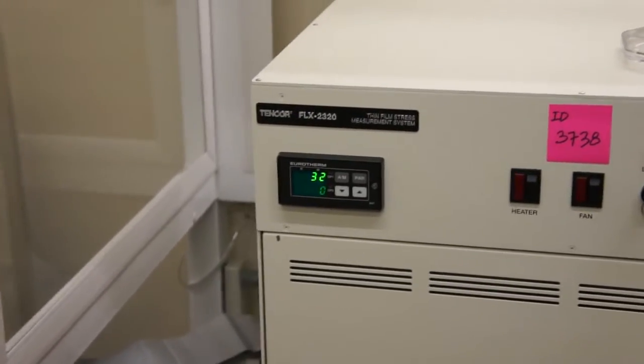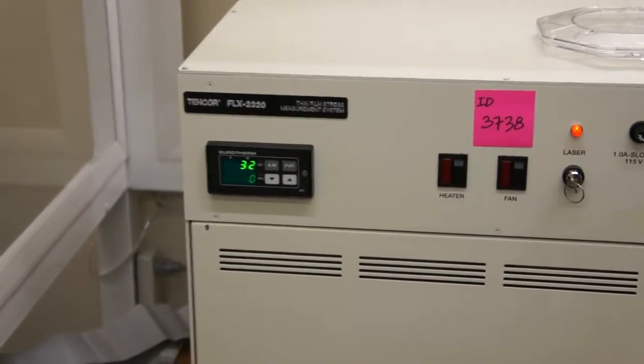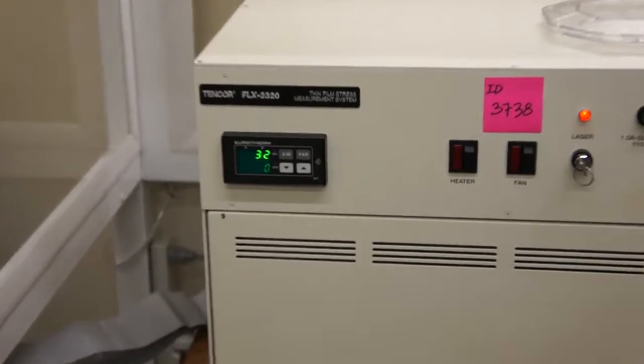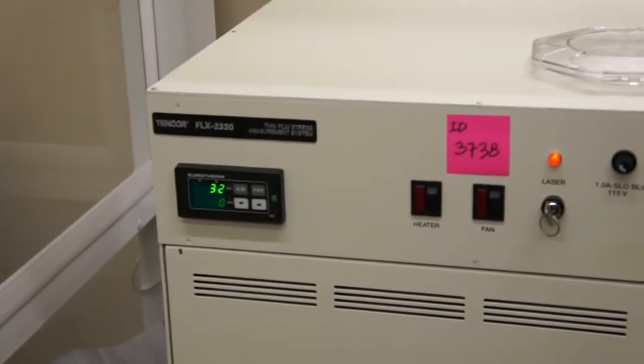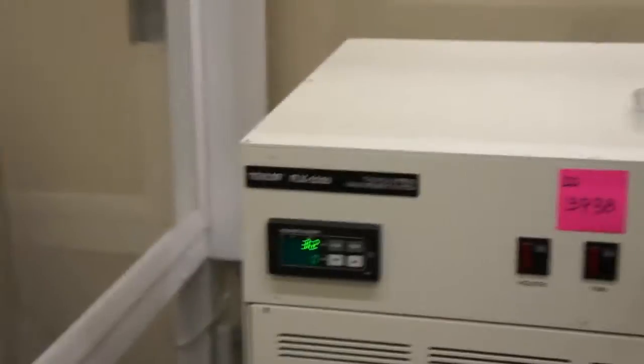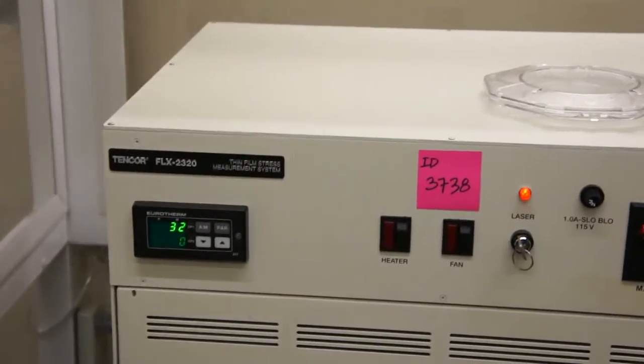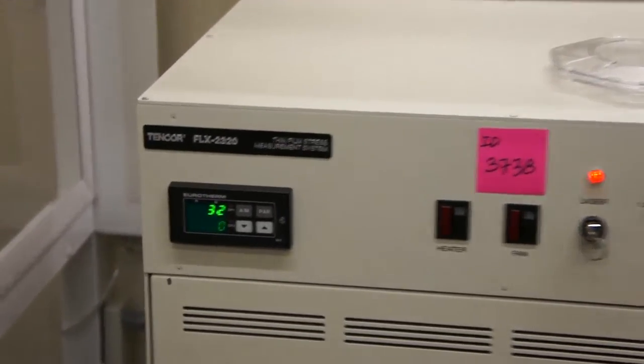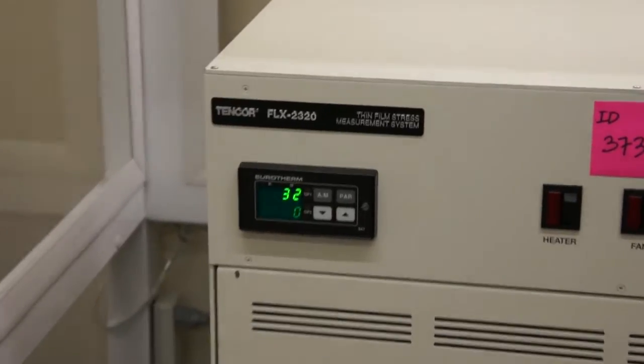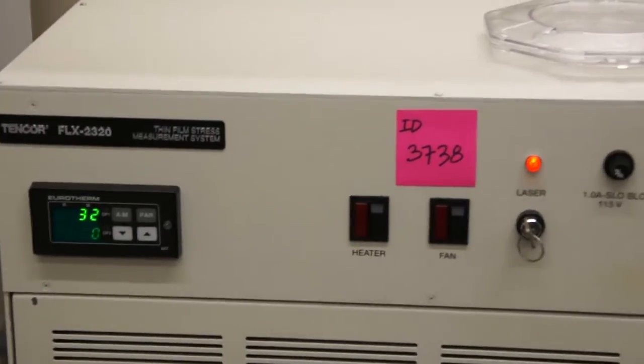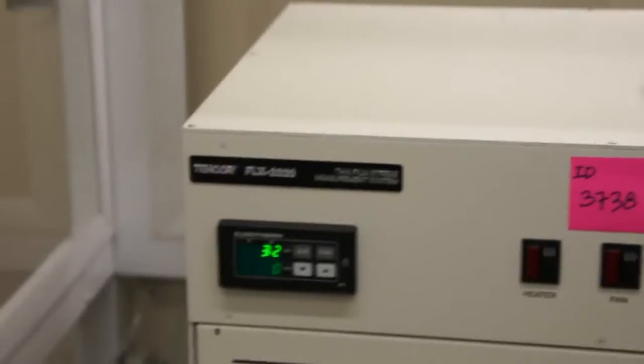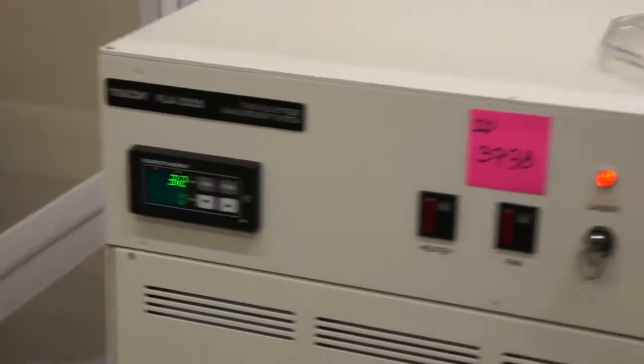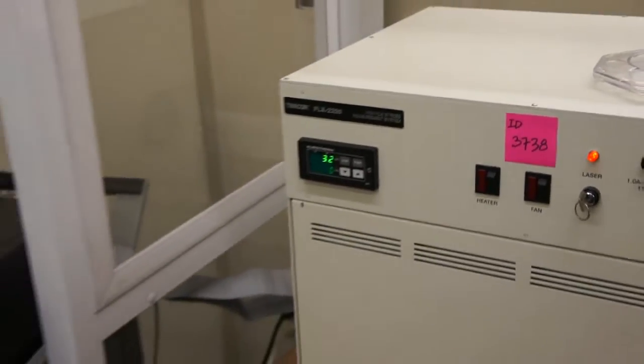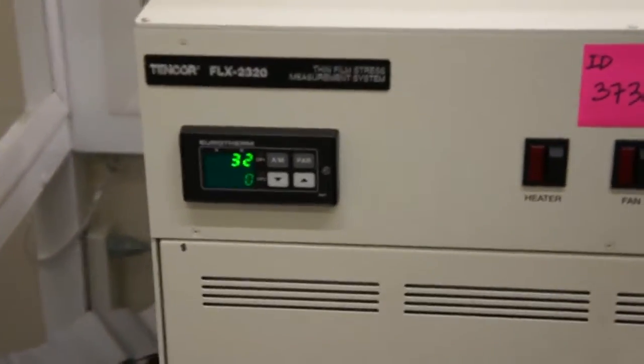Okay, a couple other things I wanted to add to the proof of life video, the demo. I wanted to point out that this tool has been upgraded from a 750 infrared laser to the 780, because the 750 lasers are no longer available as far as new units, and for any tool that needs new lasers installed and that are running the 750 lasers must be upgraded to a 780 type of laser, 780 nanometer laser.